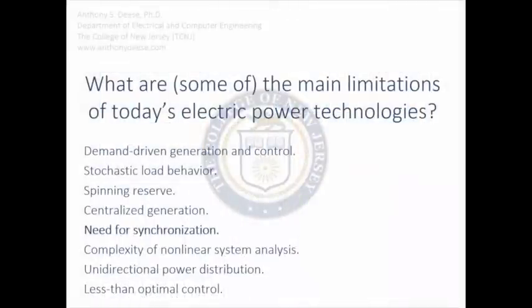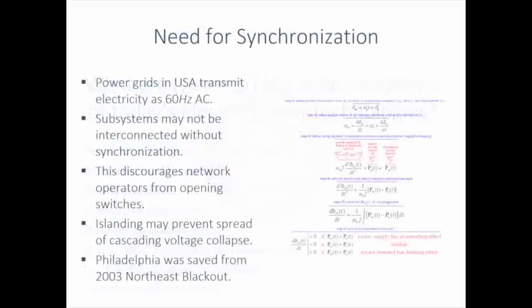Another limitation of today's electric power technology is the need for synchronization. Because power grids in the U.S. transmit electricity as 60 Hz alternating current, separate subsystems can't be interconnected without synchronizing them first. The difficulties associated with synchronization discourage network operators from opening switches to divide a large system into smaller pieces, even when islanding, as this process is referred to, may prevent the spread of cascading voltage collapse or improve overall system performance. Going back to the 2003 Northeast blackout, Philadelphia and southern New Jersey were only spared because operators islanded our network from neighbors to the north.